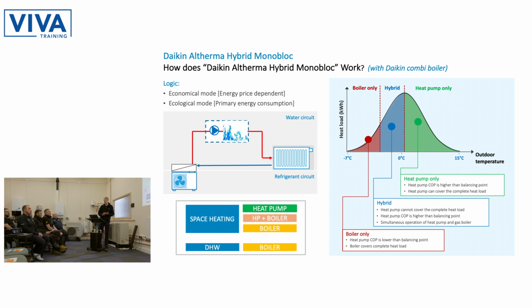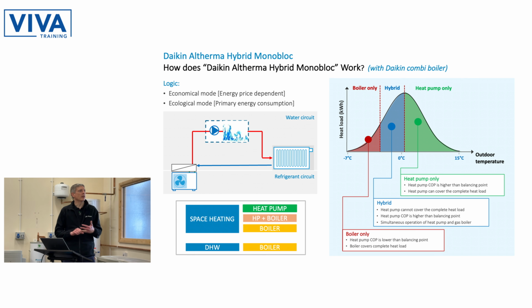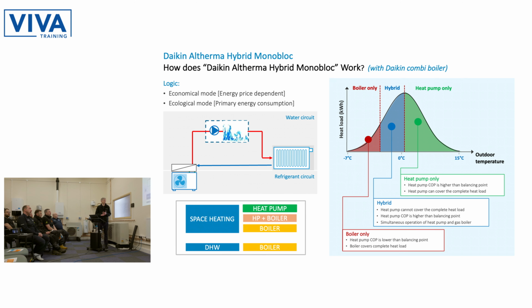It starts bringing the boiler in for hybrid operation when the heat pump can't cover the complete heat load, but the heat pump is still the most economical to operate. And then you get the simultaneous operation of both. If the heat pump is no longer the most economical, and actually gas gives the lowest running costs for the user, or you're below the operating temperature of the heat pump, outside its operating range at that particular time, the boiler will come in to cover the complete heat load for the property. But as I say, we're expecting that to be the smallest proportion of the heating requirement over the course of a year.